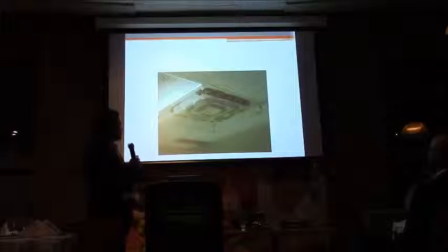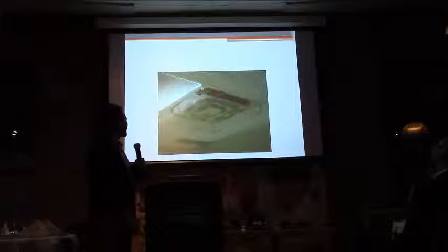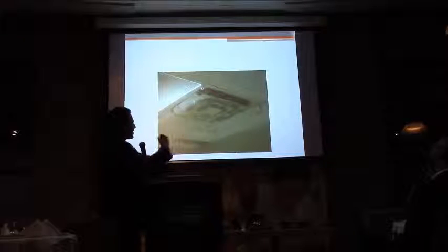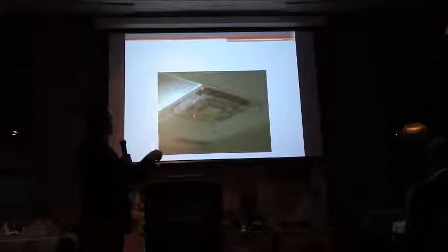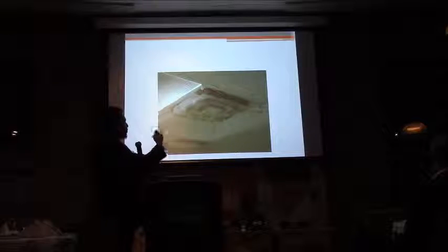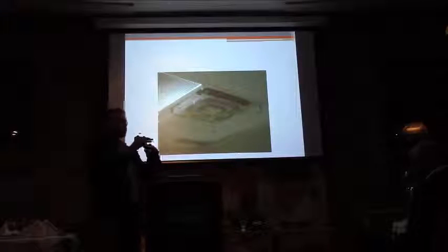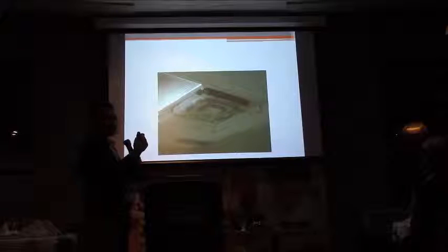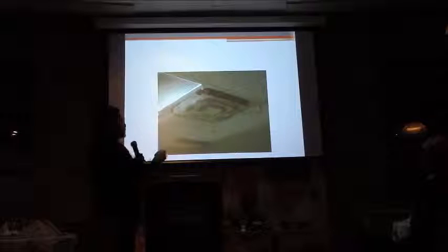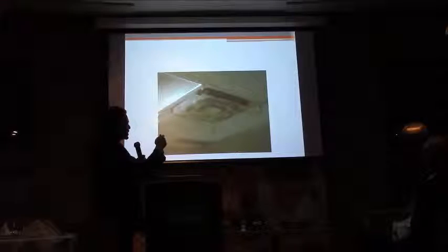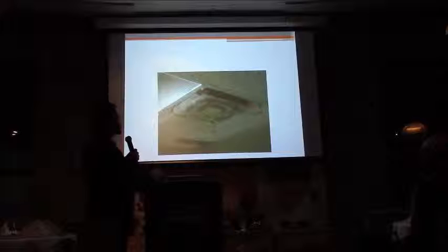So this one is actually my favorite. This happened in two steps. The first step, which I think everybody has seen quite often, is the plexiglass that's chained under the diffuser. We often see that because whenever you get that cold air shower, the plexiglass gives the air a second horizontal push, so that once it reaches the occupied zone it's closer to your set point temperature. But even that wasn't enough there, so they completely blocked the diffuser with brown paper towels.